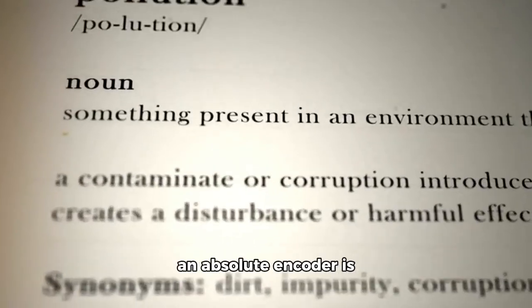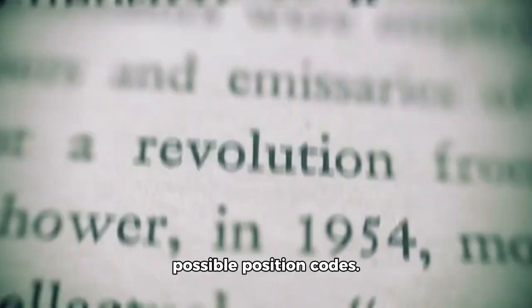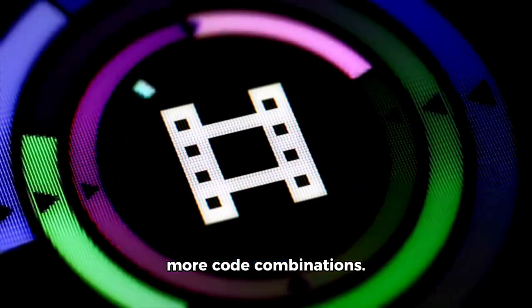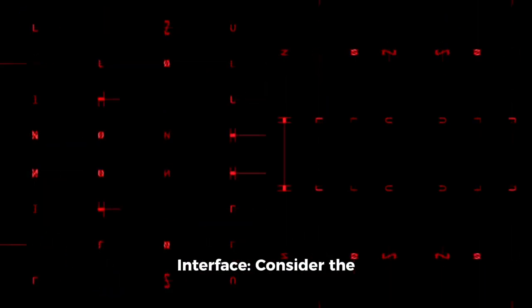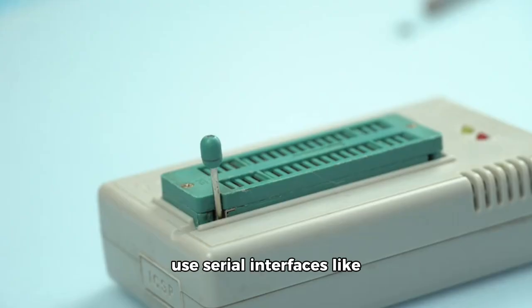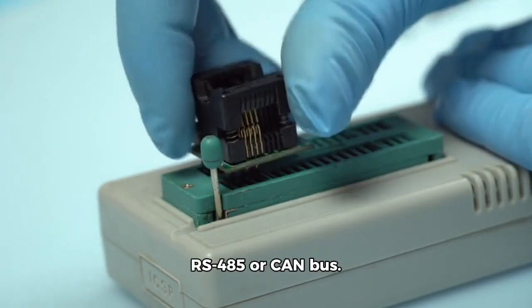Resolution. The resolution of an absolute encoder is determined by the number of possible position codes. Higher resolution encoders have more code combinations. Interface: consider the interface type, e.g., parallel, serial, quadrature. Absolute encoders often use serial interfaces like RS485 or CAN bus.